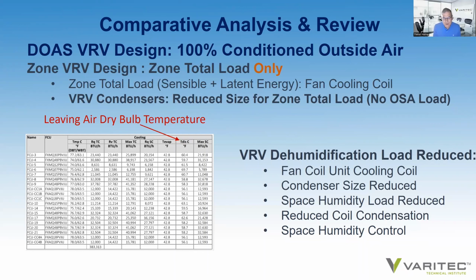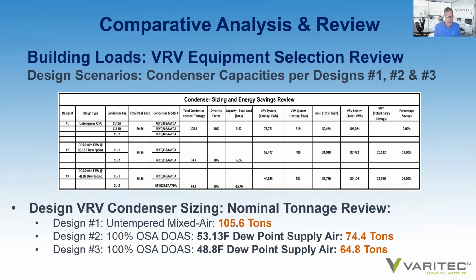In looking at the VRV design, the VRV system can be downsized. The untempered mixed air system has a nominal tonnage of 105.6 tons because the latent and the sensible load is being addressed in the VRV system for both the outside air and the building. If you have a parallel DOAS system supplying 53-degree dew point supply air, you can downsize the variable refrigerant tonnage to 74 tons. And if you provide a low dew point for a deeper humidity control DOAS solution, you can reduce the VRV tonnage to 64 tons, or 64.8 tons.